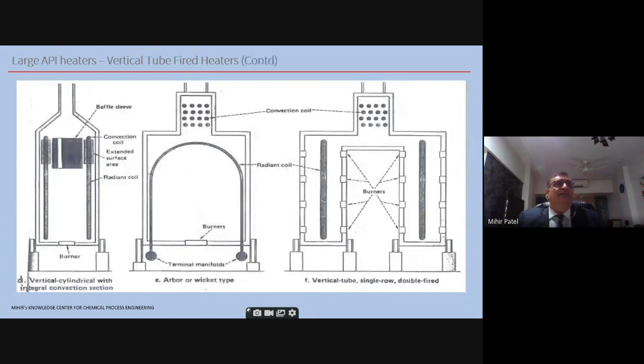Then in the vertical category you have three more: vertical cylindrical with integral convection section, the arbor or wicket type in the middle, and the vertical single row double fired type. UOP always uses the arbor or wicket type for their charge heaters, because it normally has very large gas flow and very low pressure drop. That's why this type of heater is used there. Now you need to be a little bit careful on these. The reason I said the OEM has to design this is that the burner flame should not impinge on the heating coil. That's not good.